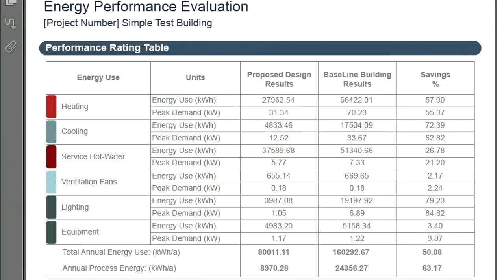The Performance Rating Table displays and compares the proposed and baseline project's energy performance; the final column presents the achieved savings. Please note that the total annual energy used of the proposed design is about half of the baseline design's, resulting in a 50% savings. Almost 60% less energy is needed for heating the designed building. The cooling-related energy consumption difference is even more significant — some flats do not require cooling systems at all due to the installed solar shading devices. Water saving taps reduce the amount of energy consumed by the service hot water heating system by over 25%. The designed building consumes much less electricity due to efficient artificial lighting and the smaller auxiliary electricity demands of the proposed building's systems.